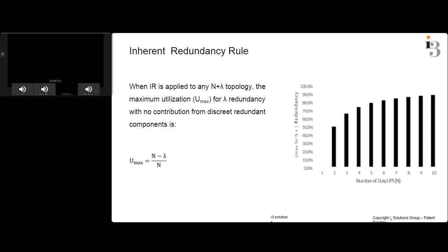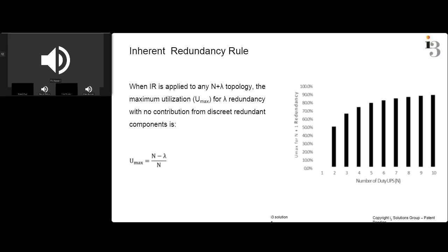Daniel, sorry if I interrupt you, it doesn't affect the SLAs at all. I should have put another drawing up for you guys to see it. But principally, no, it doesn't affect the SLAs. What it basically is saying is we use the headroom of the system as virtual redundancy. So instead of having your +1 or +2 or whatever it is, that can disappear because you have it anyway by virtue of your utilization level. It's just how do you access it, and that's kind of the secret sauce of the patent.